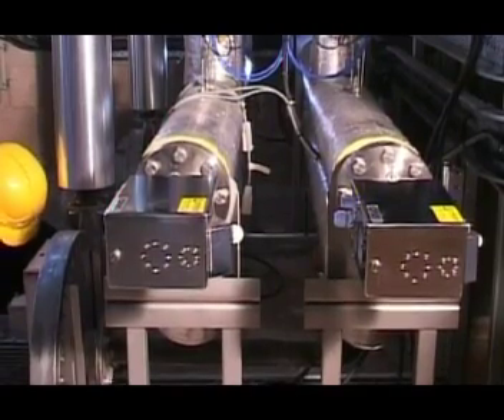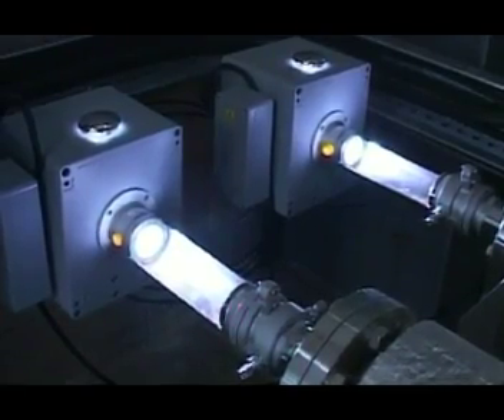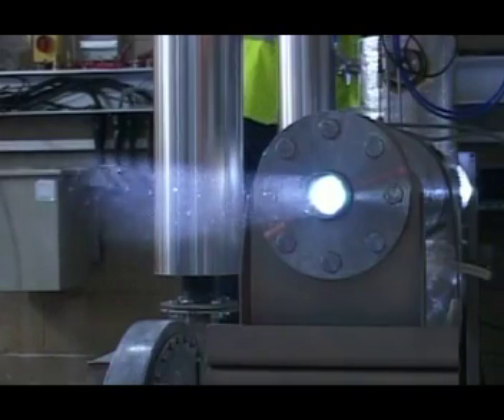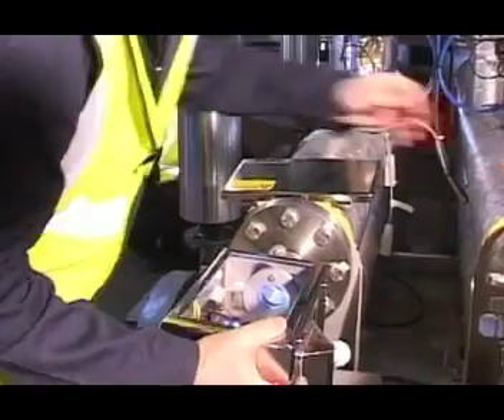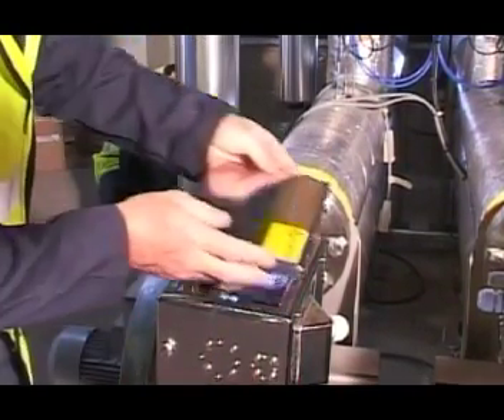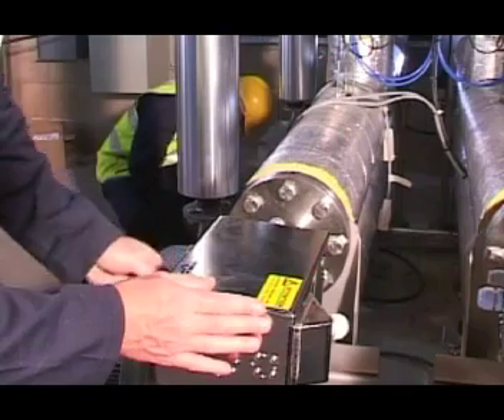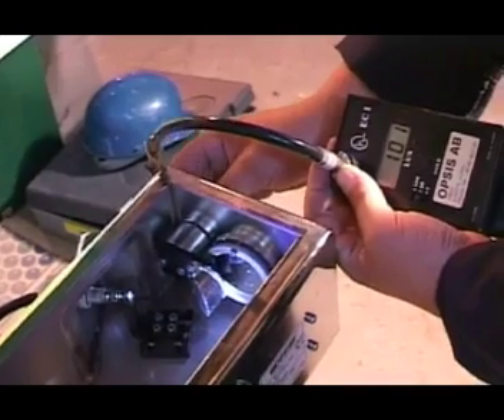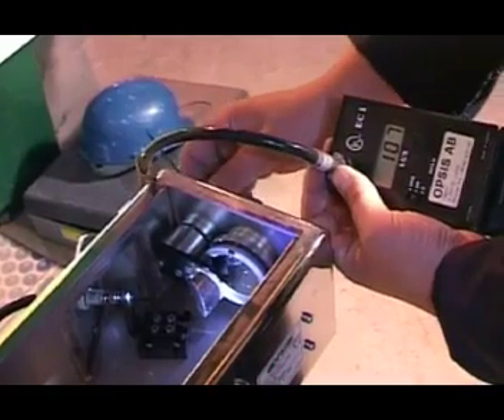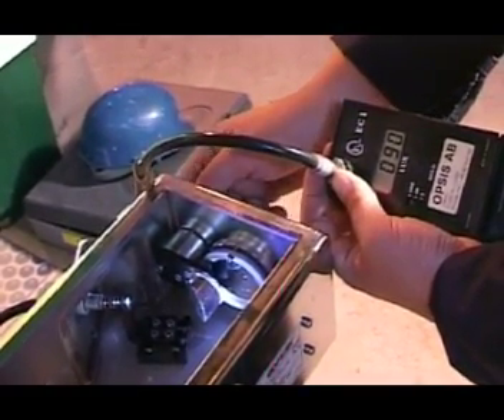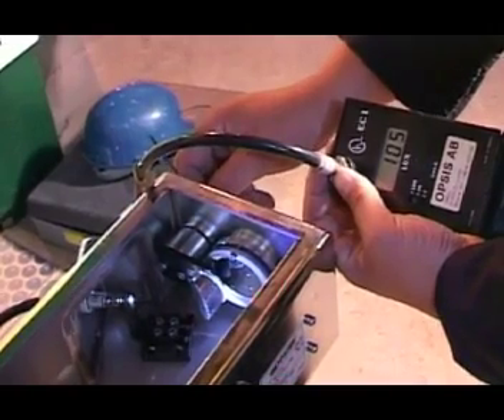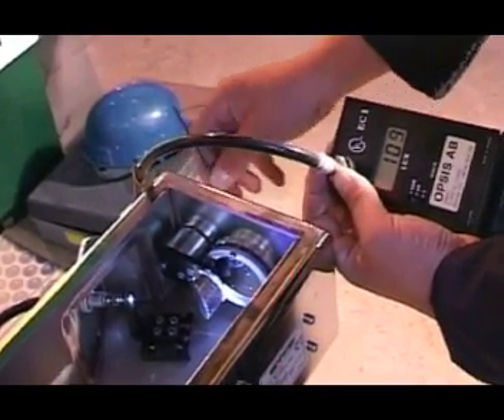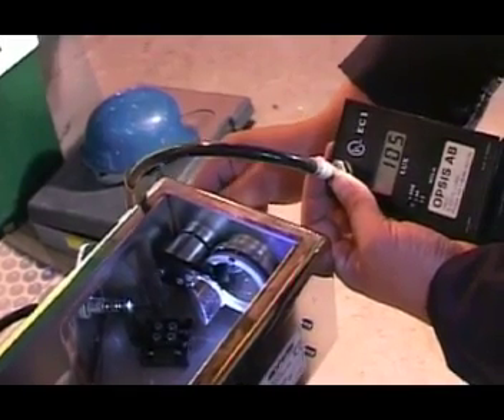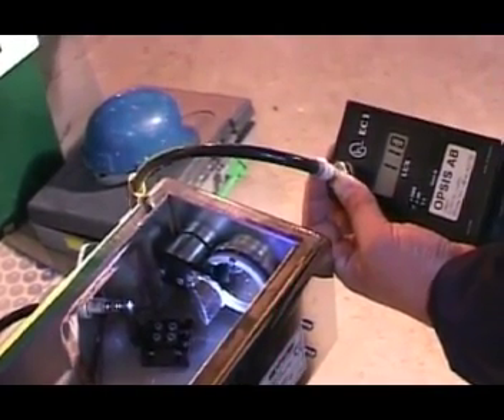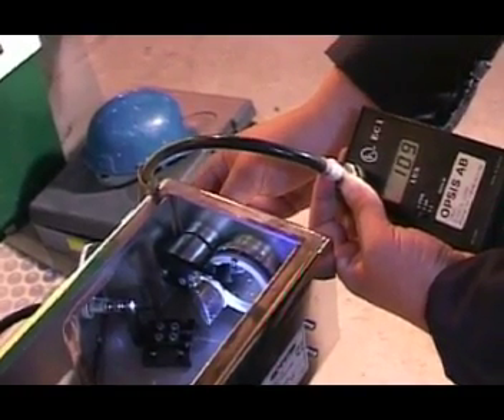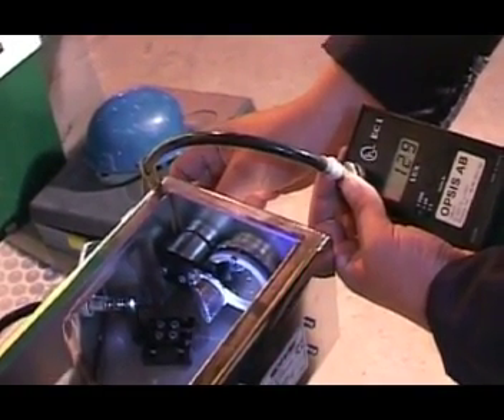We have an emitter and a receiver, and in the emitter is a xenon lamp that gives off ultraviolet, visible and infrared light. The light is transmitted down through the cell and is collected by this receiver. To enable us to focus the information or the light down to the fibre optic, we have to adjust these parabolic mirrors that are inside these two boxes. The equipment needed to do that is a fibre optic cable, which then leads up to a light meter which measures in the unit of lux. And together, moving the mirrors at both sides of the emitter and the receiver, we're able to focus down to a very small point the light that's being transmitted from the lamp.